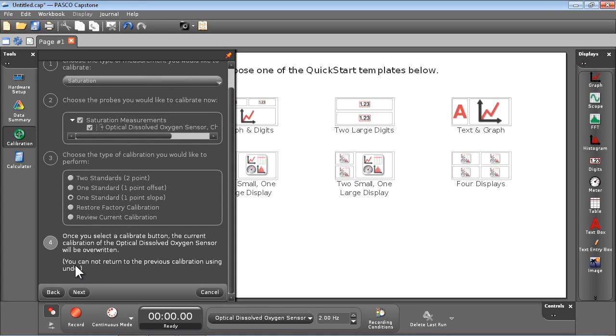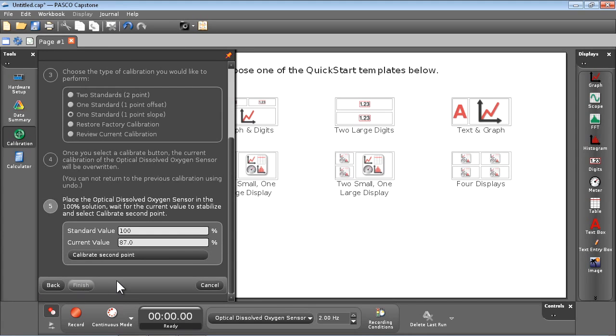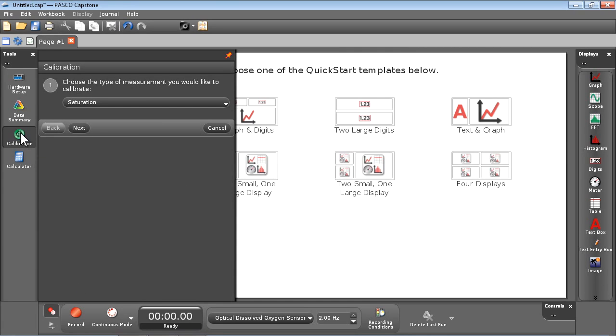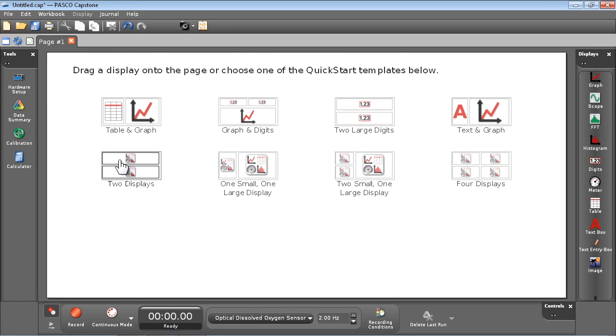Acknowledge the warning that this will overwrite the existing calibration in the sensor, and wait for the current value to stabilize. Once this is stable, select Calibrate Second Point, and then Finish. The sensor is now calibrated, and we can proceed with the experiment.